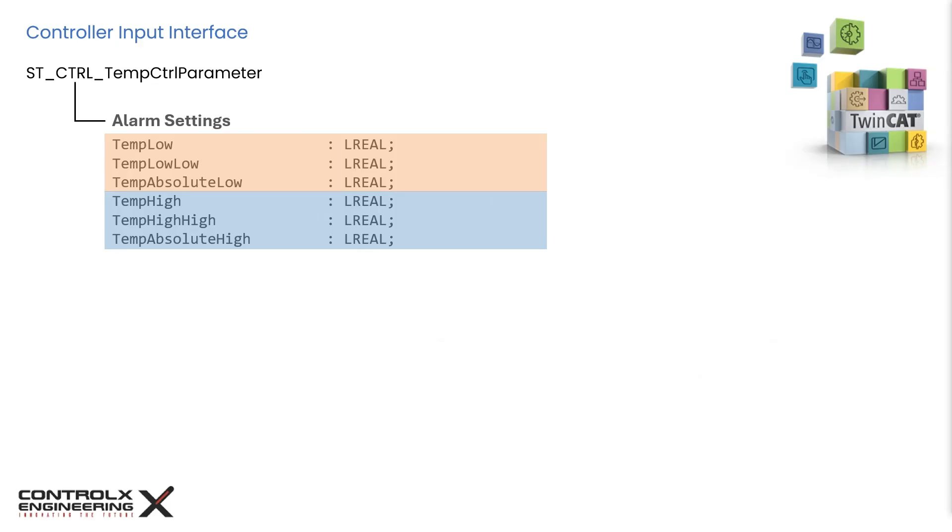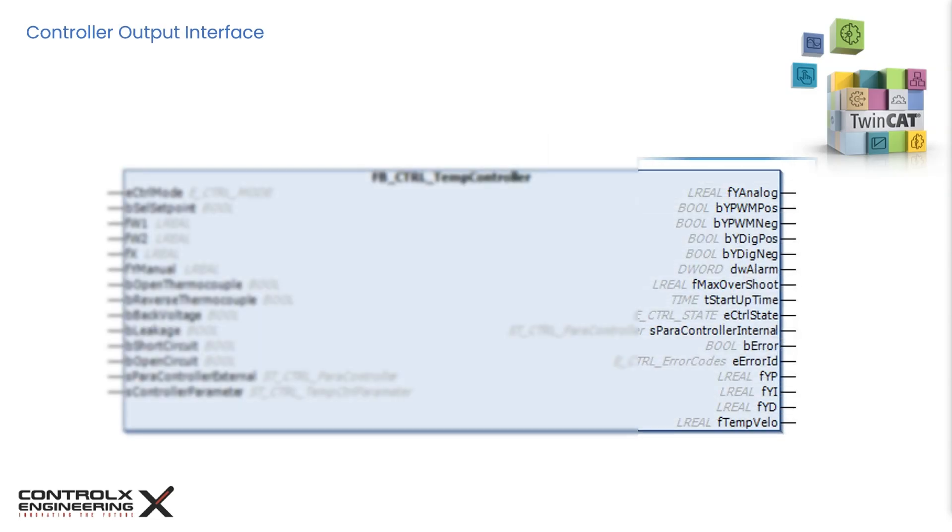These parameters control the settings for generating alarms when the temperature deviates too much. Here we can set three levels of alarms for both high and low thresholds. Now let's look at the controller outputs.